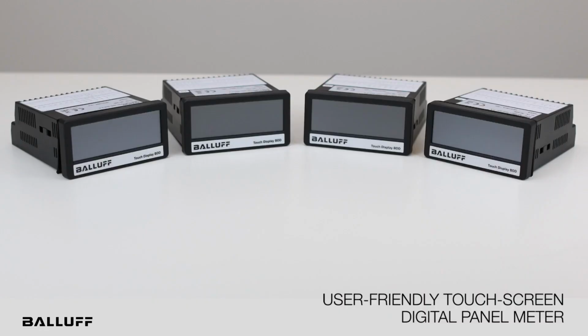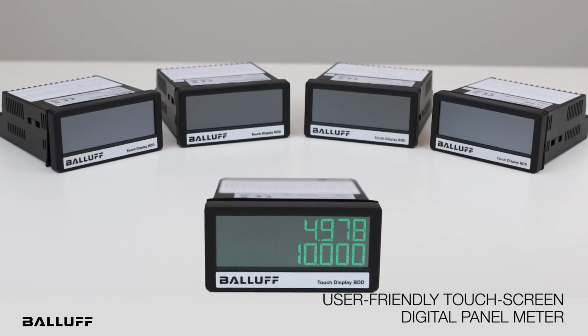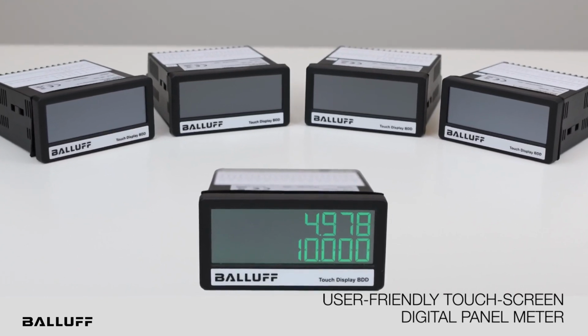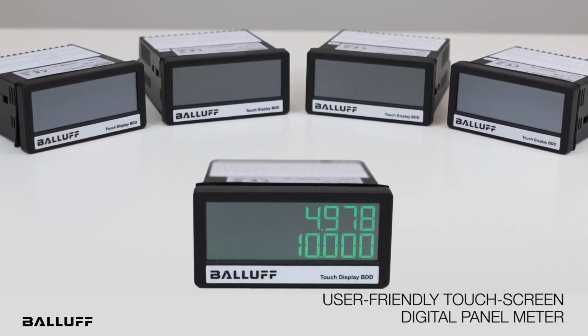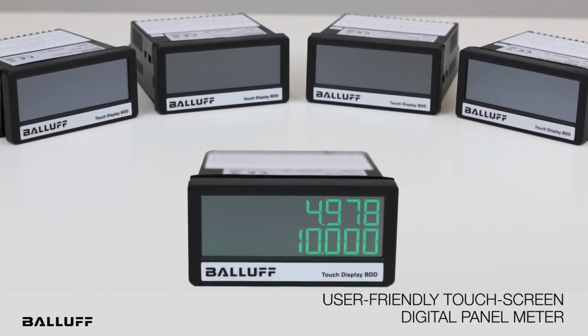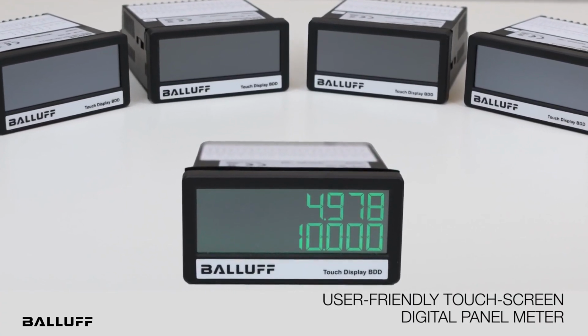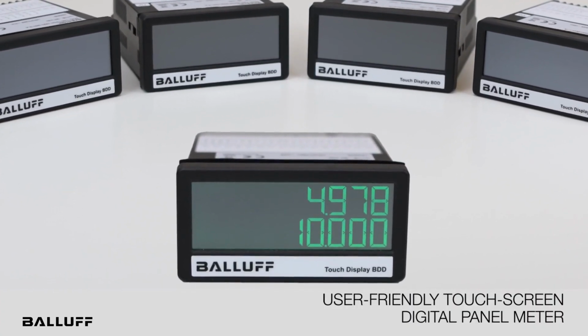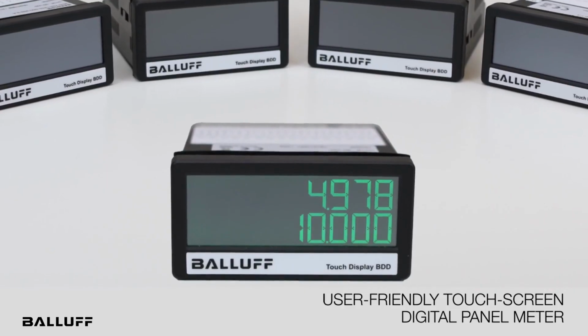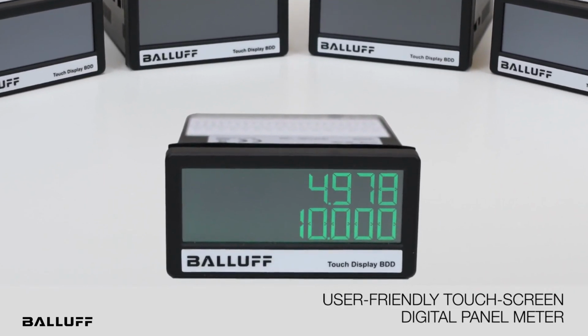Now I want to briefly highlight just a few of the more interesting and useful features of these Balluff digital displays. For starters, they offer dual input, dual display operation. This helps conserve panel space and cut costs, allowing the use of one display unit for two process signals. In addition, it's possible to display diverse conditions on a single panel meter, for example, pressure and temperature.